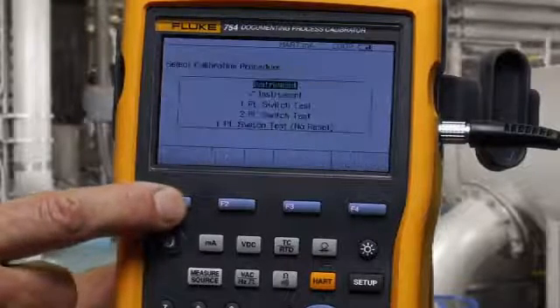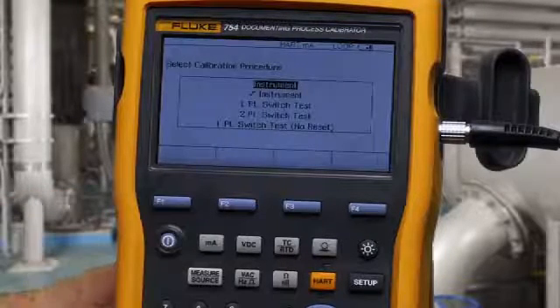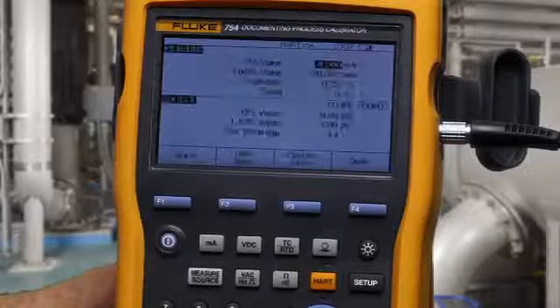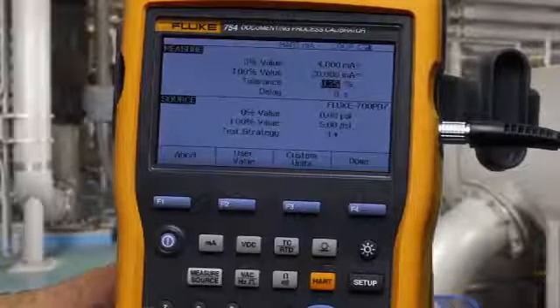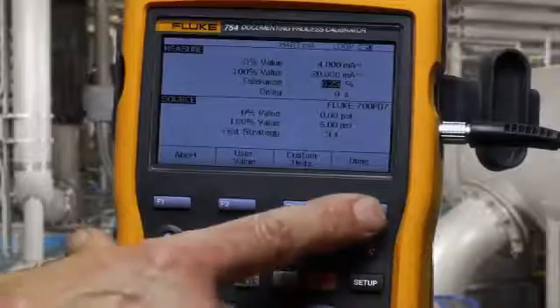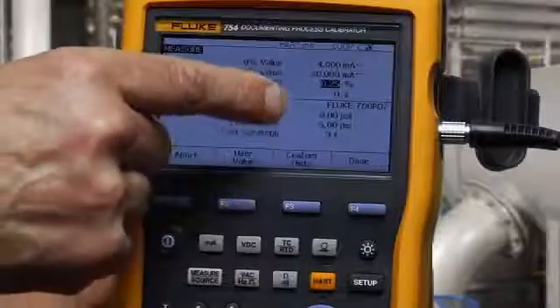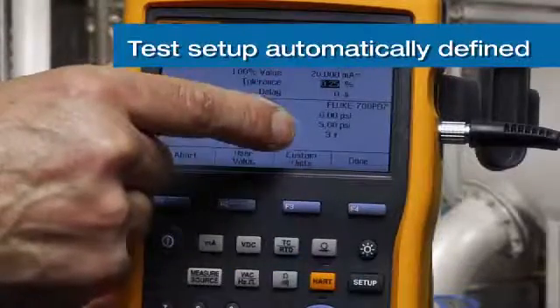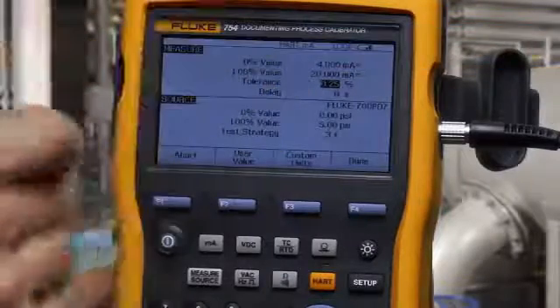To initiate the test as found for an instrument, everything is filled in. Confirm your test tolerance. You'll see the applied pressure value, zero and five PSI, for which we'll measure four to twenty milliamps to 0.25%.